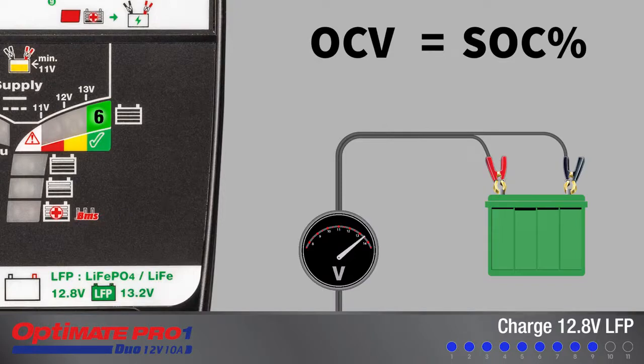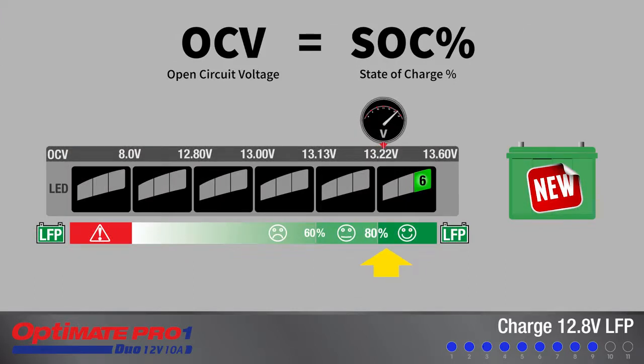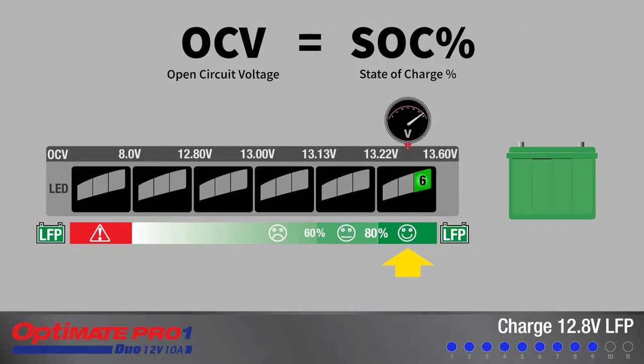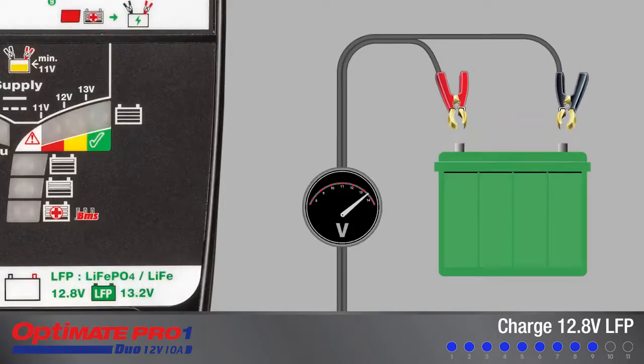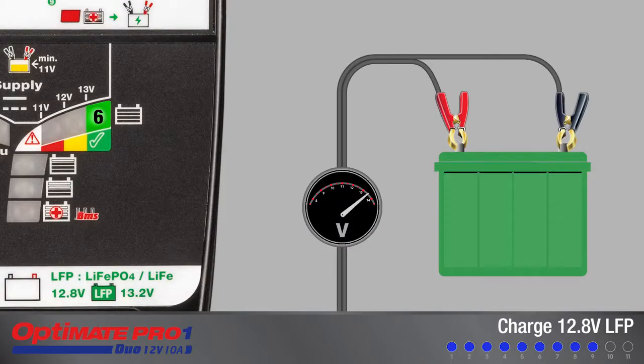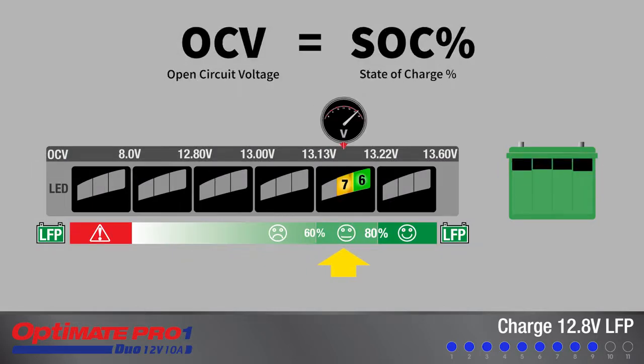The test concludes when the test LEDs 6, 7, or 8 turn full on. New LFP batteries should display between 80 to 100%. The battery is ready to be used. No further charging is required, but if left connected, the program continues to step 10 for a final cell balancing charge. If the panel displays a 60 to 80% result, the battery may have lost capacity, but it is still serviceable. Leave connected to proceed to step 10.